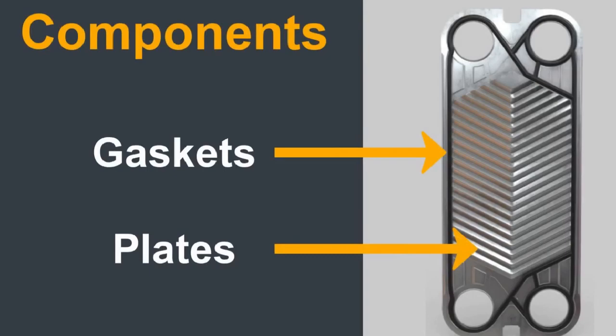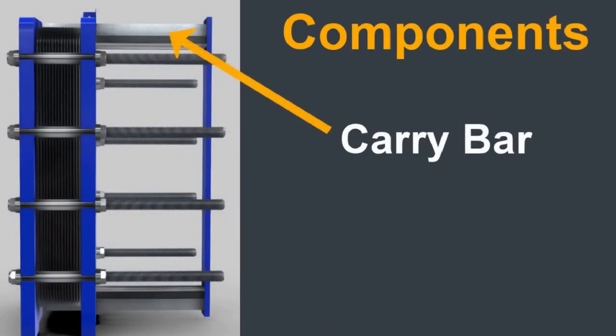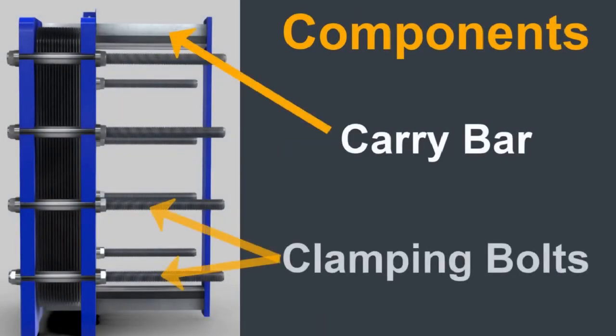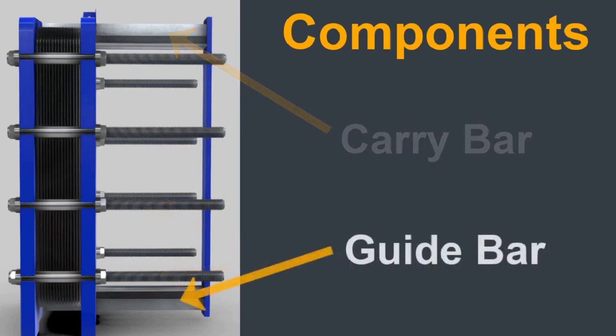Gaskets and plates are used to separate the flowing mediums and prevent them mixing. The gaskets are adhered to one side of each plate only. The plates hang upon a carry bar and are pressed together using clamping bolts. When the plates are compressed together, they form a plate stack. A guide bar ensures the plates are aligned correctly when the plate stack is opened and closed.